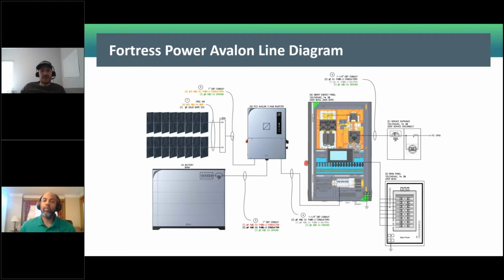Yeah, so the basic flow and the basic overall installation is you have your main that goes straight up through a couple CTs right here built into the smart energy panel. And so your main ties straight in. You have a spot for those PV breakers. So for the inverter, the inverter connects over and lands in the panel straight on a 200 amp bus bar. So it is a 200 amp pass through, regardless of whether you have the 7.6 or the 11.4.